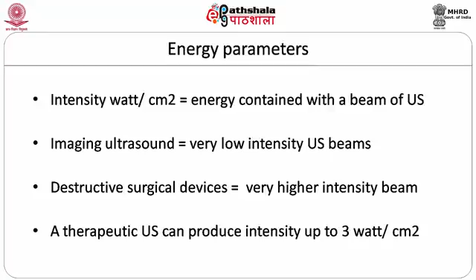Intensity describes the energy content of the ultrasound beam. It is measured in watt per centimeter square. A therapeutic ultrasound can produce intensity up to 3 watt per centimeter square. Imaging ultrasound uses a very low intensity ultrasound beam, but in destructive surgical devices, a very high intensity beam of ultrasound is used.